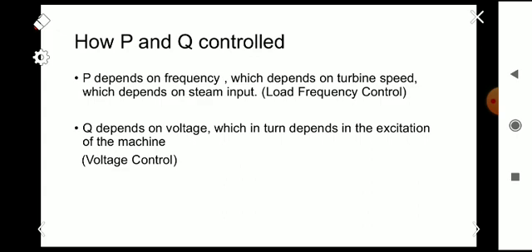How can P and Q be controlled? As we know, active power P depends on frequency, so for controlling the active power we are controlling the frequency. Frequency mainly depends upon the turbine speed, which depends upon the steam input. So for controlling P — the active power — we are controlling the steam input to the generator.